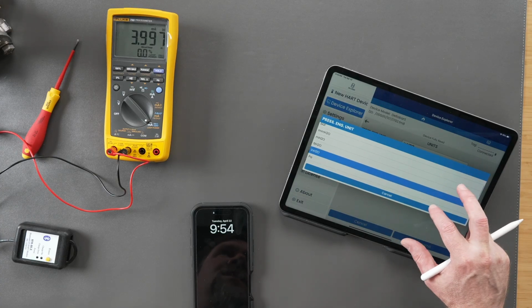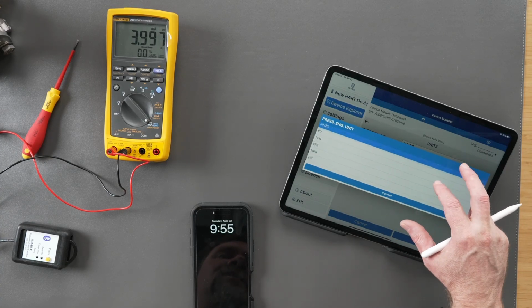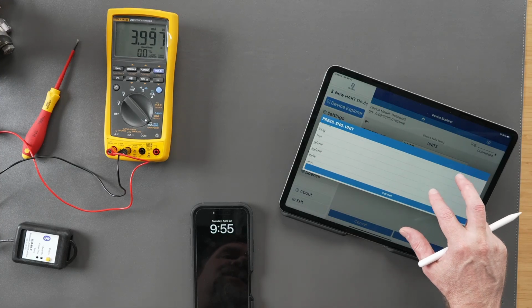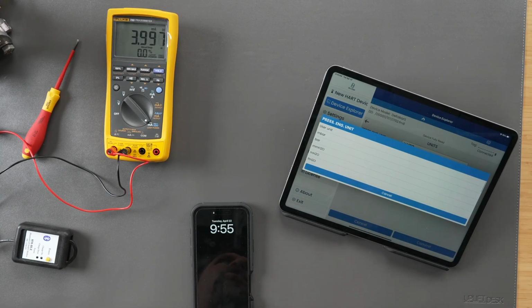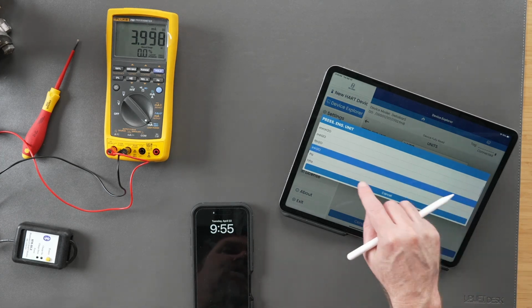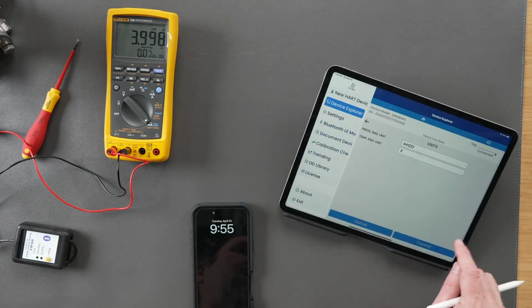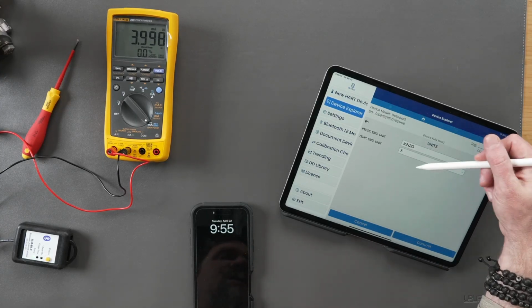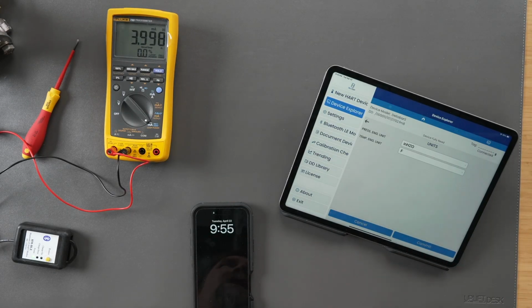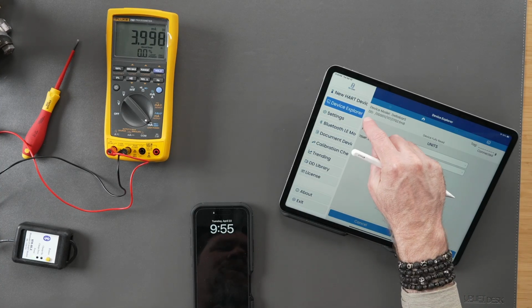You can see there are a lot of different units possible, from PSI and on, but think about it. This is a raw pressure measurement. You're not going to find percent of level. You're not going to see gallons a minute if you were doing a differential pressure for a flow. These are the raw pressure measurement units, okay? So in this case, we're going to stick with inches of water column. Degrees F, that temperature is how hot the sensor itself is, so it's not one that we're using to program or do any kind of calculations. It's just looking at how hot the temperature is getting.